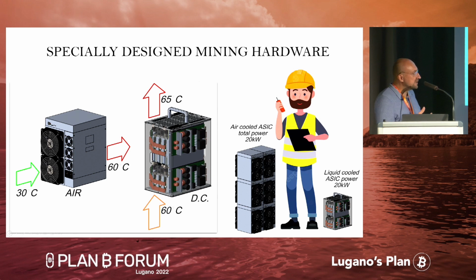This means we can work at very high liquid temperatures, which explains why our cooling system is so capable - there's a huge difference between the liquid target temperature, 60 degrees in this case, and even on the hottest day the air outside will probably be 45 or 50. So we have a 15 degree difference, which is enough to cool that liquid from 65 back to 60. This is why our system is so capable.